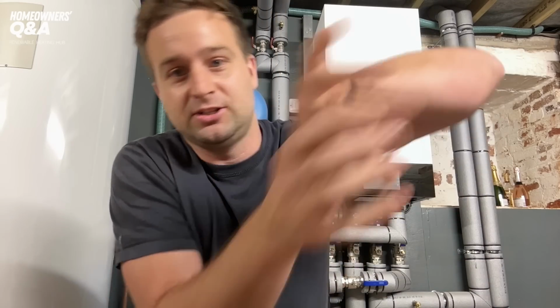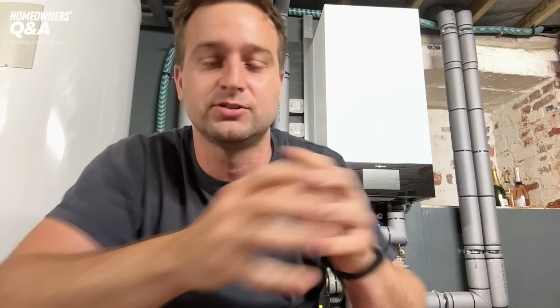Yeah, I think you've got it, Mark. Say you've got a 6 kilowatt heat load downstairs, and each rad is 6 kilowatts. You should have the same flow rate going to each radiator. Let's just keep it simple for a second. When water goes down that pipe and the first radiator is there, or it needs to go down this really restrictive pathway to the other radiators, loads of flow, as much as it wants to, is going to go to that first radiator in theory. So yes, and balancing is trying to make that more restrictive. If you imagine the furthest index radiator is very restrictive, you're trying to balance that valve to the same thing, without talking about the flow rate required for each emitter.